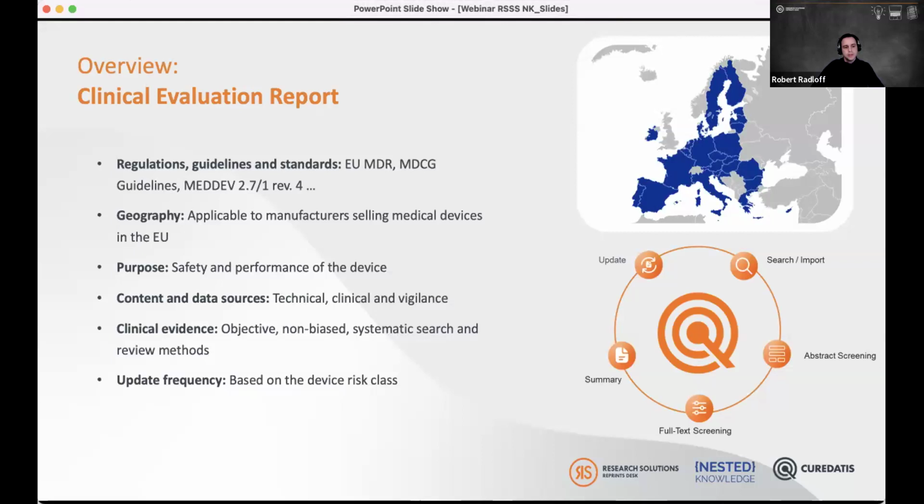And every manufacturer who is selling medical devices in the European Union needs to comply with those medical device regulations. So there needs to be a clinical evaluation report for every device. The purpose of this clinical evaluation is to show the safety and performance of the device. In the end, the content of a clinical evaluation is a digest of the technical documentation. So there's a technical part about the device, the clinical part, so the clinical evidence, but also vigilance data for the device. So that's a very inhomogeneous type of paper in the end.